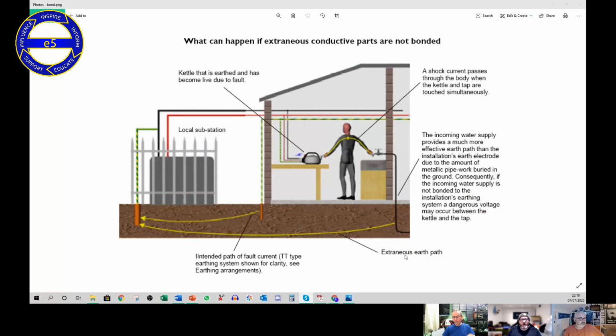There we go. All right, so we've got an illustration here of the extraneous earth path underneath. Yep. So supplementary bonding would often be recommended to that tap to equalize the voltage between the exposed conductive part of the kettle and the extraneous conductive part of the tap, which means that voltage would not travel across. Now, we've omitted the need for supplementary bonding, however, most of the time, with sockets having RCD protection and that kettle being supplied from them. So the way the regulations are now written is supplementary bonding could be omitted if we have this kind of protection.